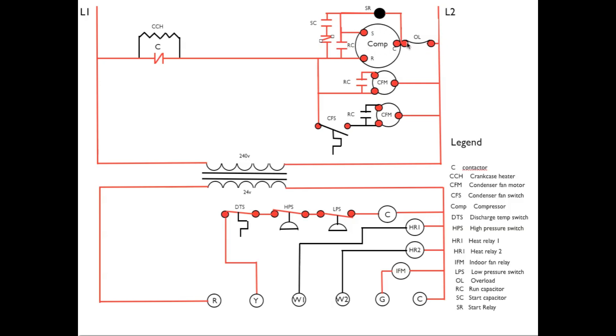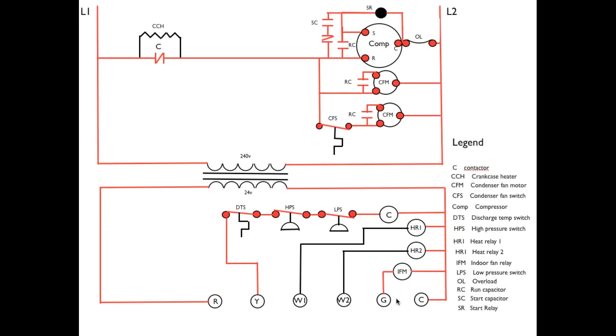If the compressor is drawing way too much power, then OL will open up. This all happens at the same time Y gets energized. Power will also pass from R to G through the thermostat to energize the indoor fan motor.